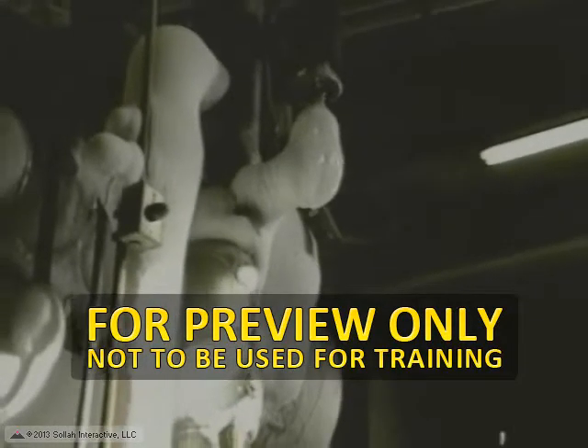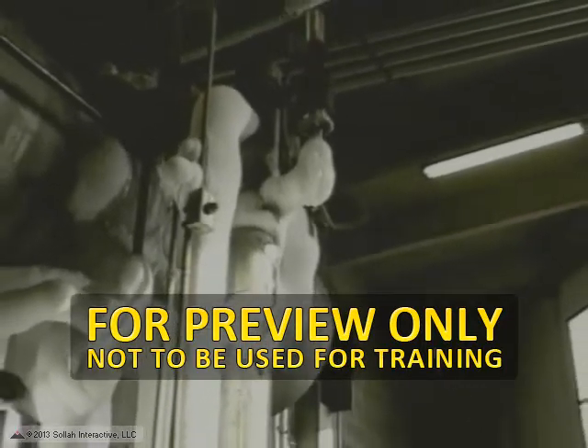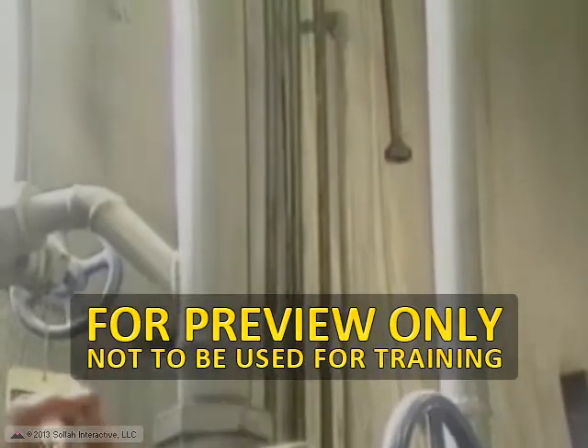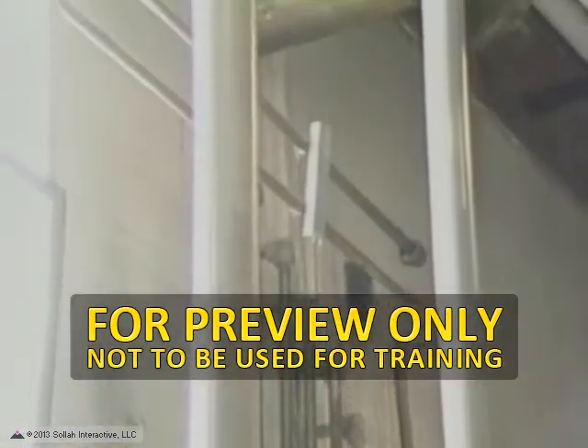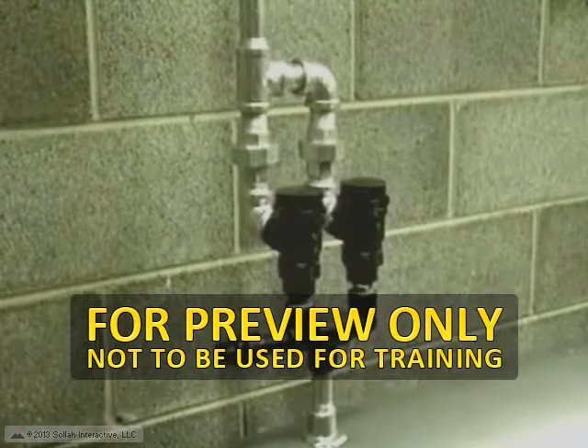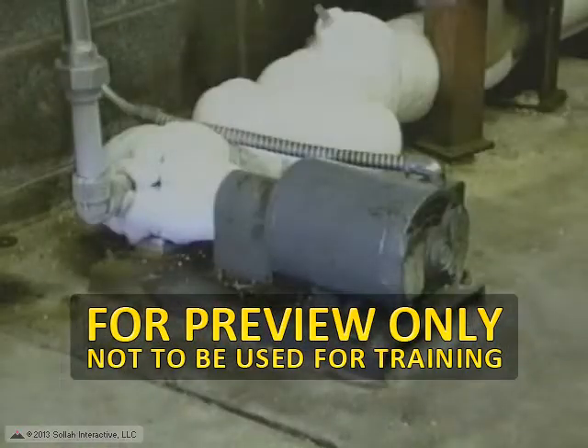Many systems also contain a low-pressure liquid receiving vessel. The pressure storage vessels are attached by fixed piping. Piping and valves are used to direct the flow of liquid ammonia to the cooling units. Both vessel types will contain pressure relief valves, which function if pressure inside the vessel exceeds specifications. If a low-pressure receiving vessel is utilized, a low-pressure liquid pump will be present in the vessel.